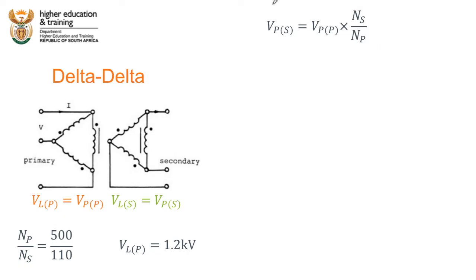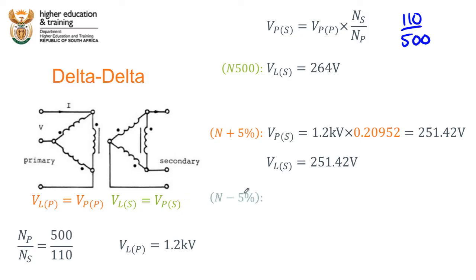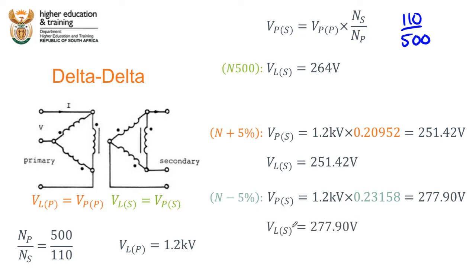For delta-delta with tappings: at the 500 V tapping we already know the line voltage is 264 V. At the plus 5% tapping, the turns ratio is 0.20952, giving a secondary phase voltage of 251.42 V — and since secondary is delta, line voltage is also 251.42 V. At the minus 5% tapping, using ratio 0.23158, we get 1.2 kV × 0.23158 = 277.90 V for both phase and line voltage on the secondary.